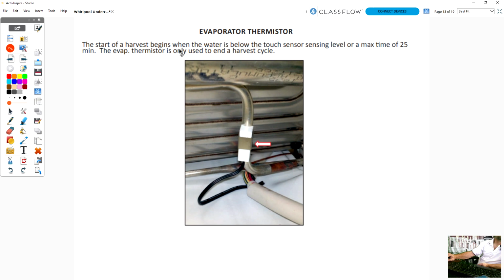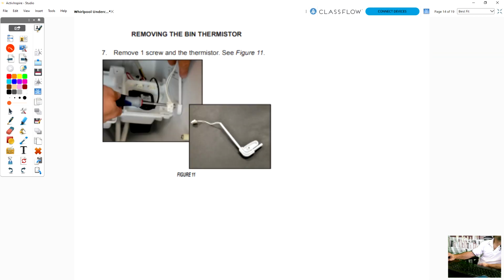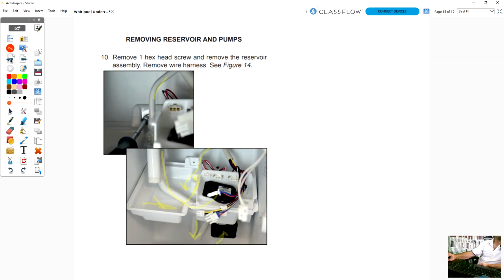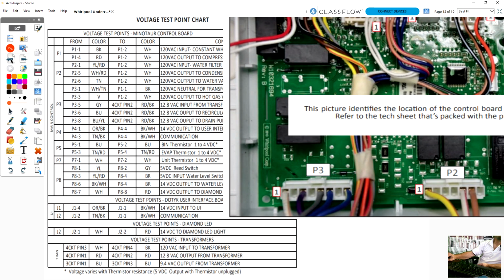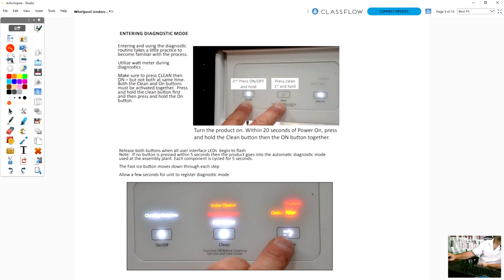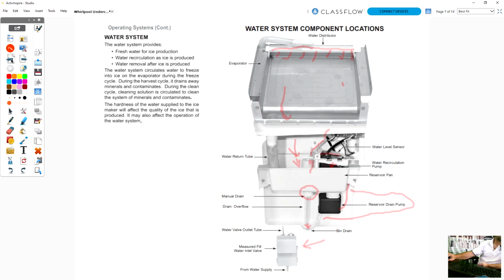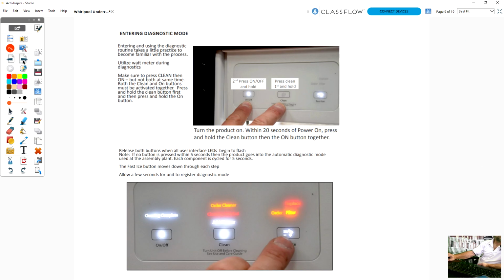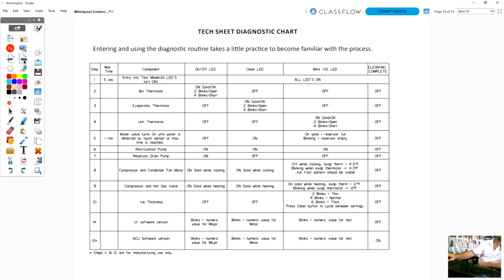The start of the harvest begins when the water level is below the sensor, or at a max time of 25 minutes. I think I saw somewhere it said 54 degrees. So once that sensor notices that there's 54 degrees on that suction line, it's going to stop the ice harvest cycle and then reinitiate the ice production.